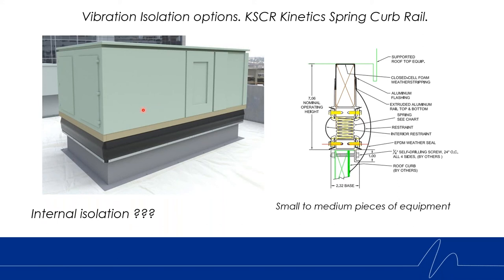These units come with what's called a shipping lockout, so the fan isn't bouncing around on the springs when the unit is being shipped to the job site. We must leave that shipping lockout in place to make sure those springs aren't active, because spring on top of spring can make the vibration and noise worse — it can actually resonate. So internal isolation needs to be locked up, but you're going to get all the isolation you need from the spring rail itself.